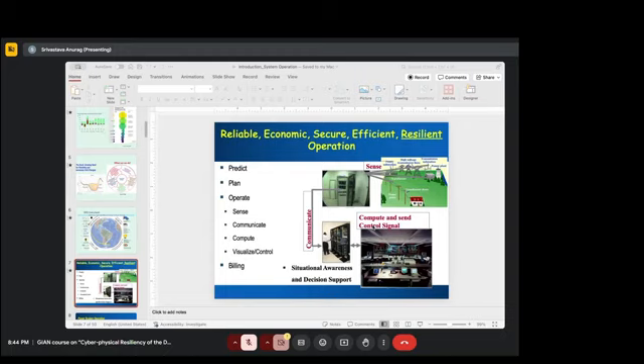In terms of deployment, at least in the US, almost all control rooms for distribution do have state estimation, depending on the size. If it's a large distribution system, they are running state estimation. For very small systems, they are not running state estimation because they have more issues - if you don't have enough sensors, you cannot do state estimation, which is typically the problem with distribution system operation.